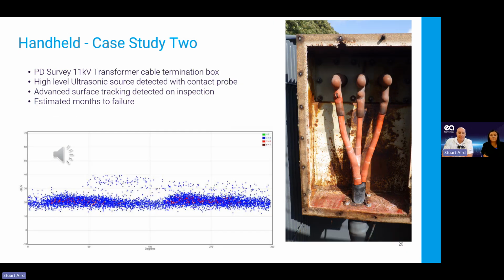The next one is some transformer cable termination boxes. Again, we've picked it up with a surface related partial discharge, and we can hear it. Again, I'll play that for you. It's not quite as distinct as that one. This was actually detected with a contact probe in the field.